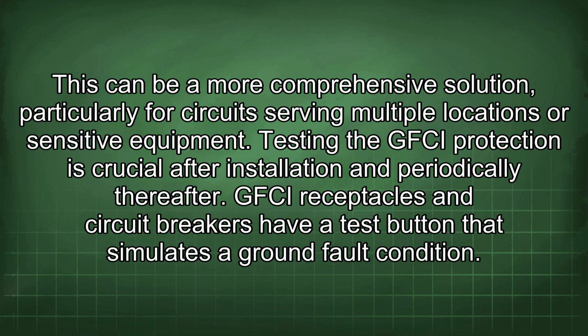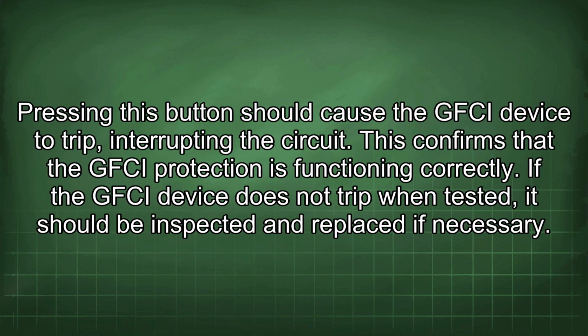Testing the GFCI protection is crucial after installation and periodically thereafter. GFCI receptacles and circuit breakers have a test button that simulates a ground fault condition. Pressing this button should cause the GFCI device to trip, interrupting the circuit. This confirms that the GFCI protection is functioning correctly. If the GFCI device does not trip when tested, it should be inspected and replaced if necessary.